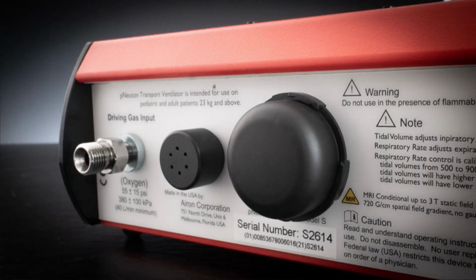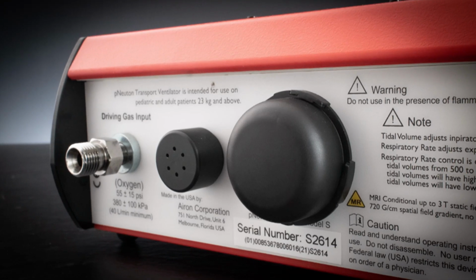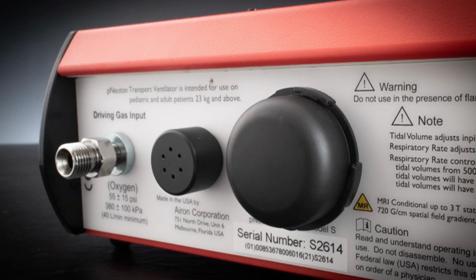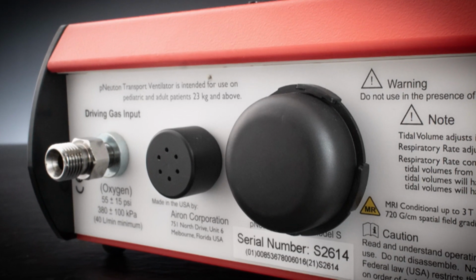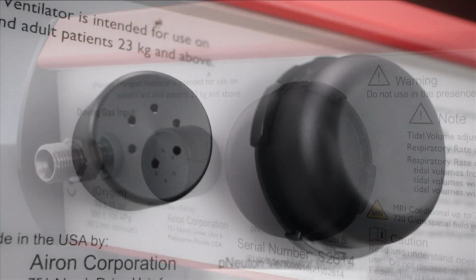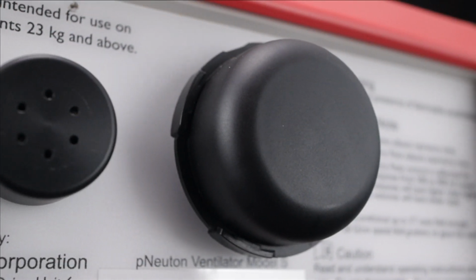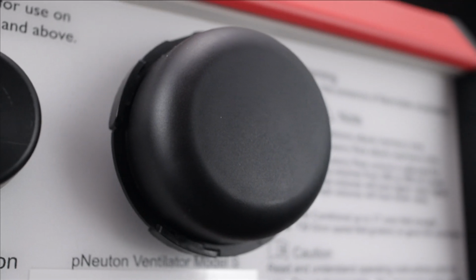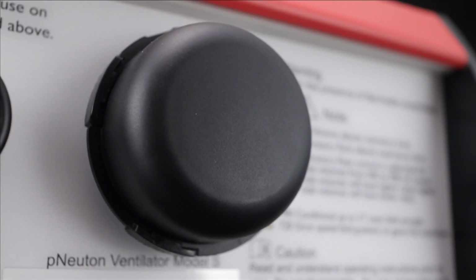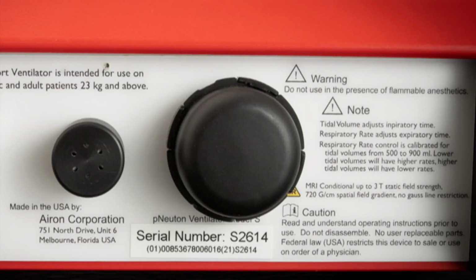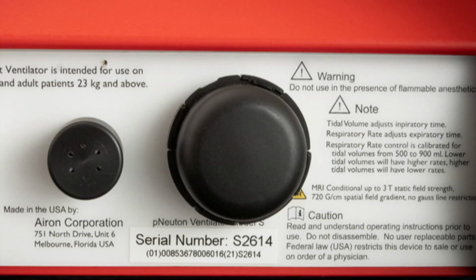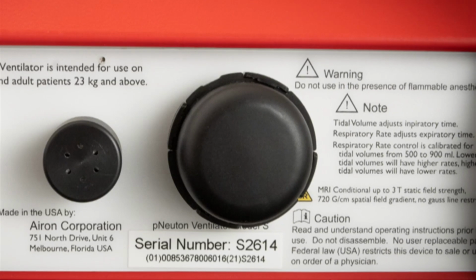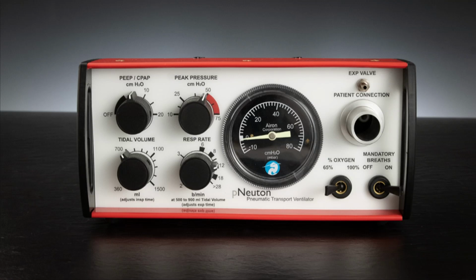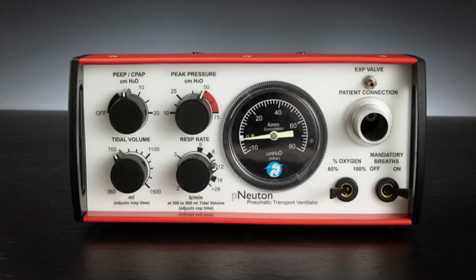Air intake and filter. The third item on the back of the unit is the filter for the ambient air intake. Airon Corporation will change the filter during routine preventative maintenance, which is required every 2 years. The filter can also be fitted with a nuclear biological chemical filter, also known as an NBC filter, for use in hazmat situations. Now let's move our attention to the front of the pNeuton Model S.